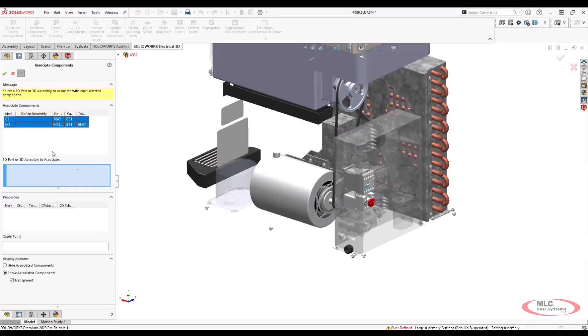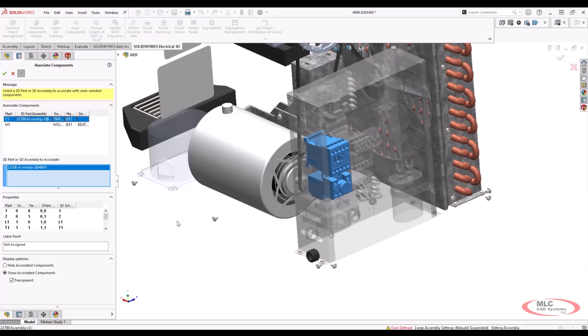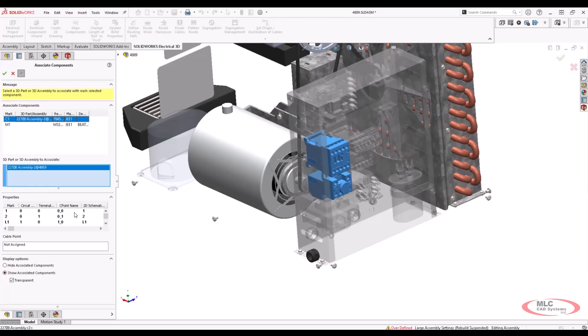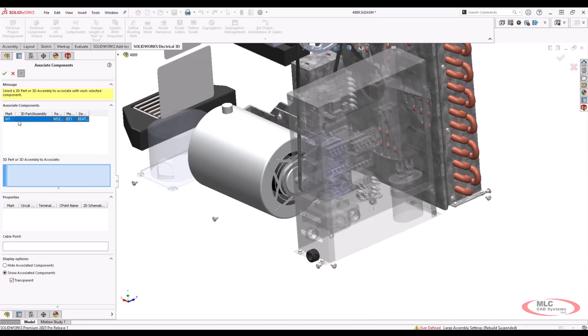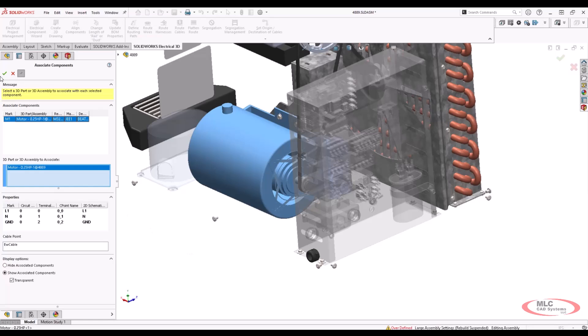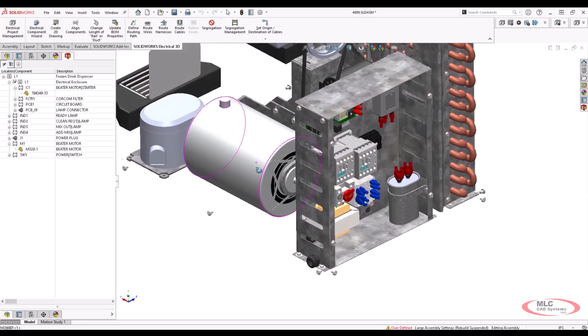I'm going to re-associate the contactor and motor. Highlight them just like before and go to associate. The new thing they've added is the ability to do both at the same time. I'll left-click on the contactor — it shows all my connection points, mark data, circuitry, how many terminals. I'll hit the green check for C1, and while still in the same tool I can go ahead and select the motor and hit green check again. Very quickly and efficiently you can multi-select as many components as you need, associate them, select the one you're working on, hit green check, and keep going to the next one. They really streamlined that.